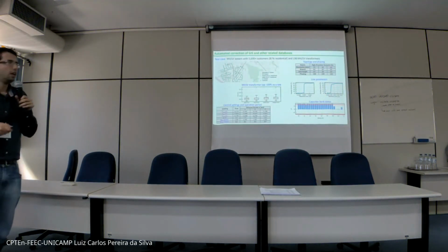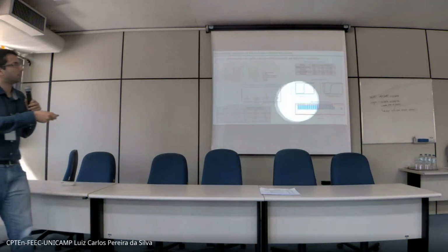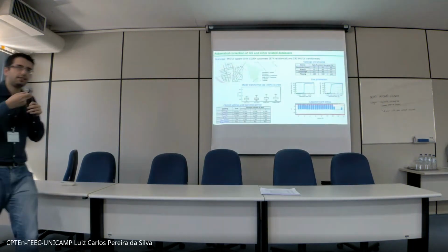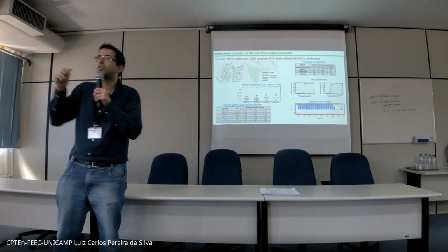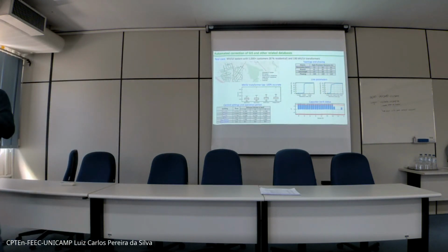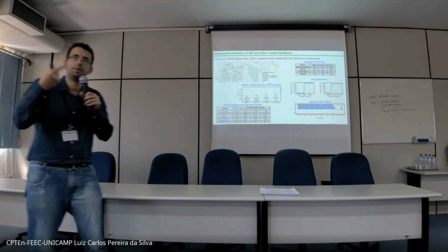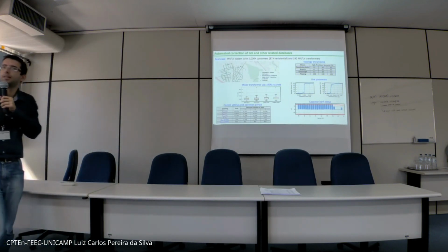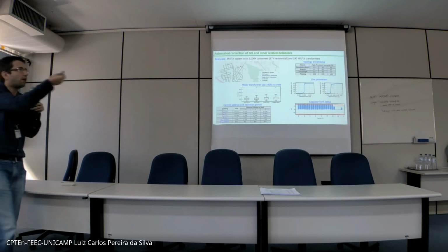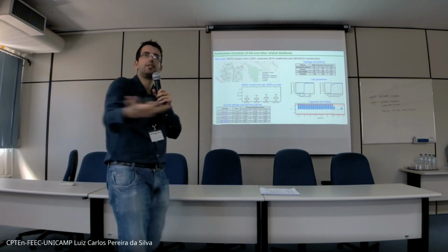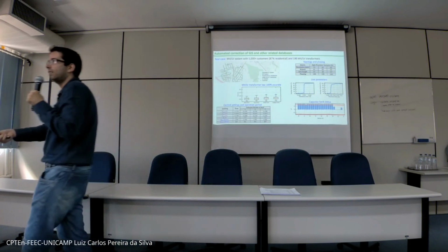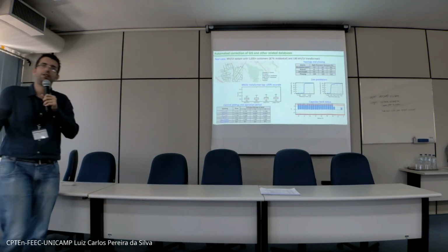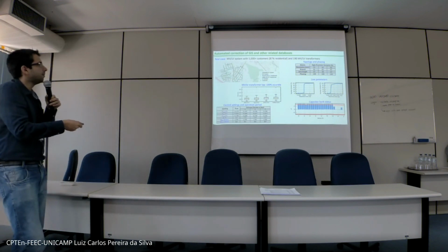If you have smart meters on all low voltage customers, you can perform topology and phasing correction. Many times the utility database topology is not updated, as the circuit undergoes reconfiguration all the time and the database is not always updated correctly. You can help correct this database based on voltage, active power, and reactive power measurements all over the grid. You can also detect tap changes in the transformers.